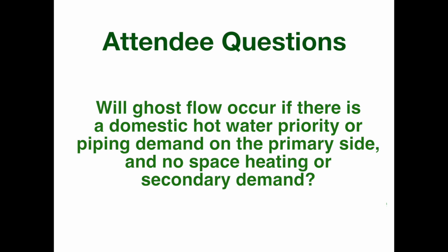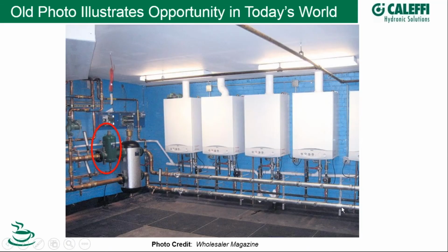Okay, that's an interesting question. So I think it's a good question. So I'm just going to pop this installation here. If we have, and disregard the air separator over here, a hydraulic separator and we have a domestic hot water demand connected into our system, let's say it's on our primary side, all right, and coming back, it could be on our secondary, but most commonly you would connect your domestic hot water on your primary side, ensuring the highest temperature water being delivered to the hot water heater.